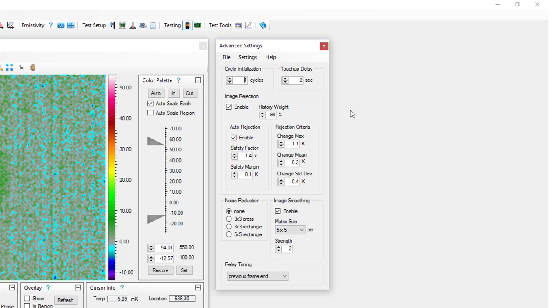For the majority of lock-in tests involving low levels of heating, cycle initialization should be set to zero cycles. Unless image artifacts become apparent in lock-in images after touch-up calibrations, touch-up delay should be set to two seconds.